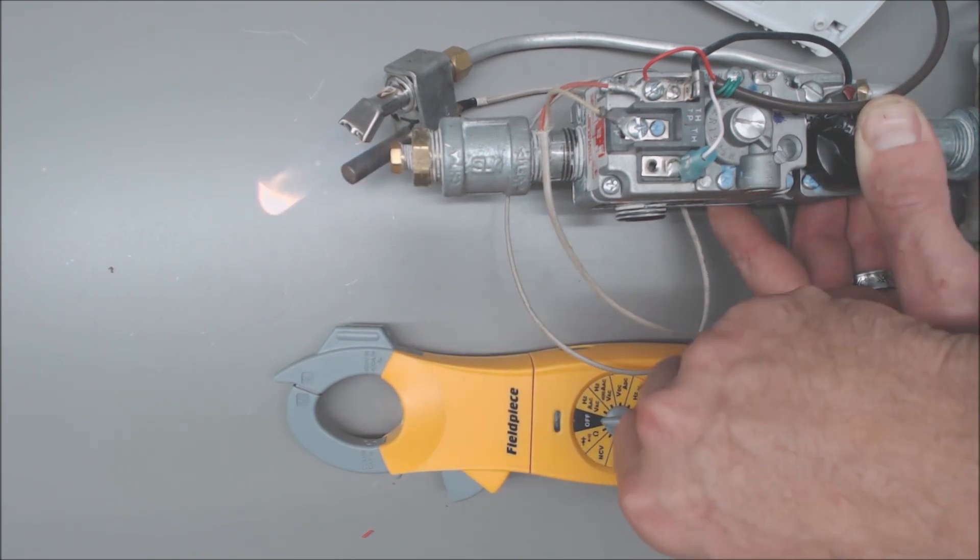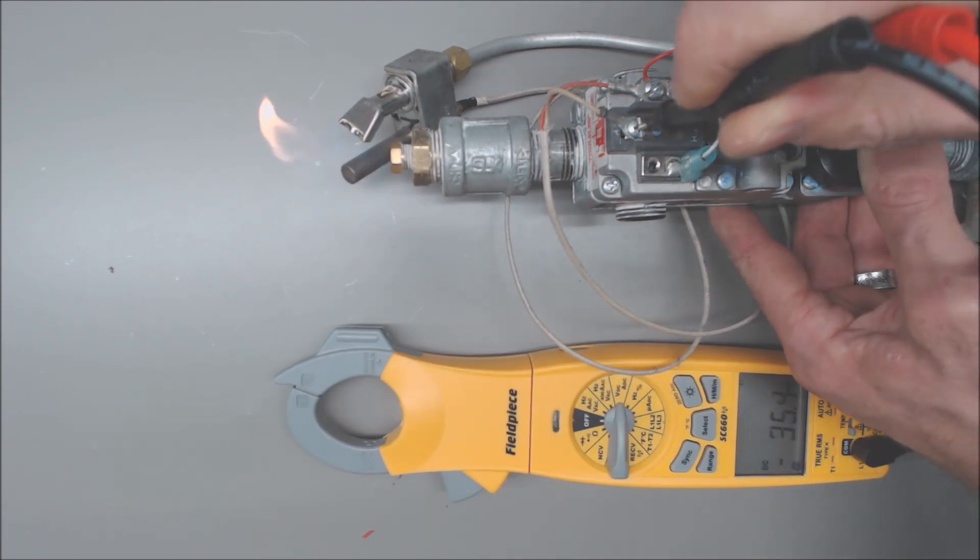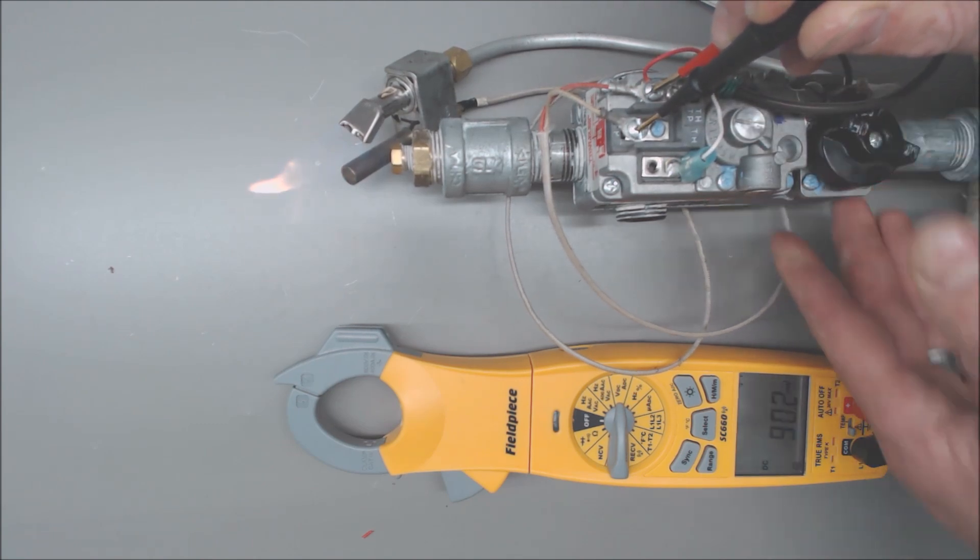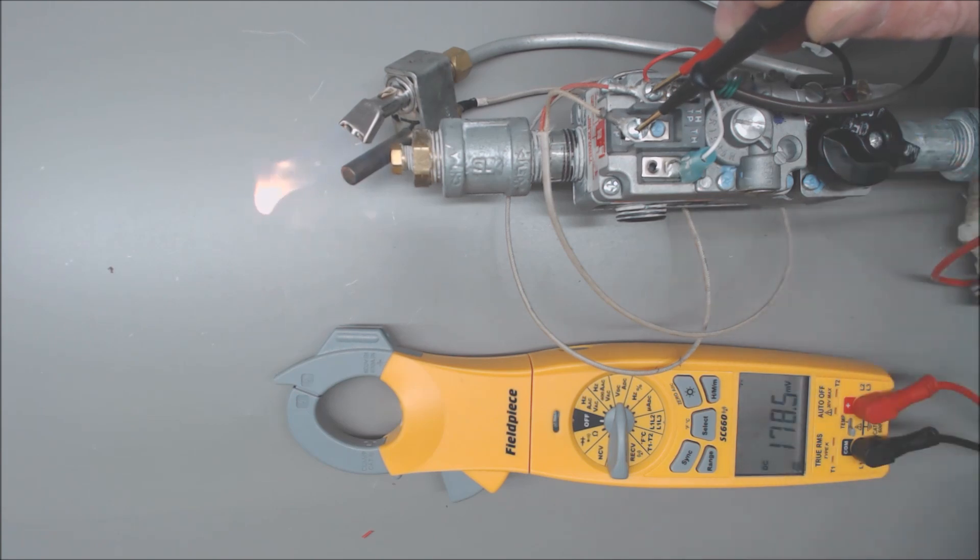We're going to take a DC millivolt reading right on our connections here, and you see that we're reading above 60 millivolts. That means that pilot valve is actually stuck open right now. See, I no longer have to press this down.